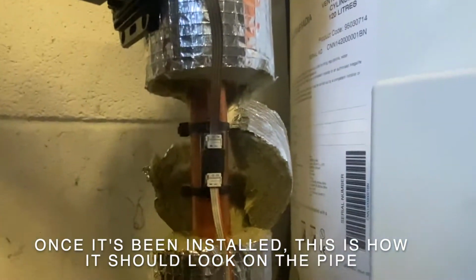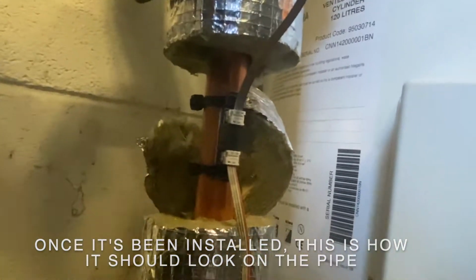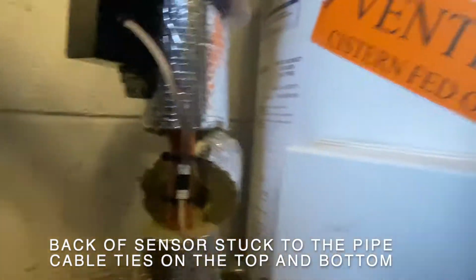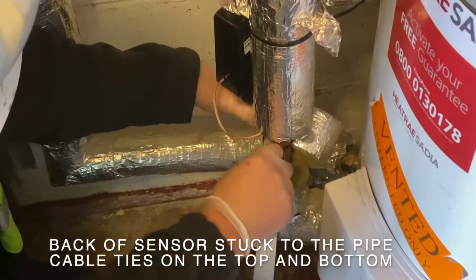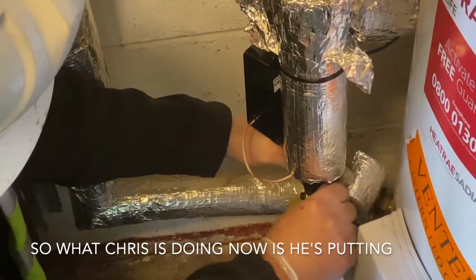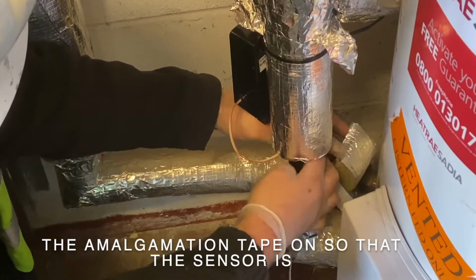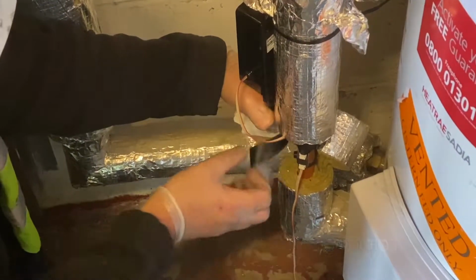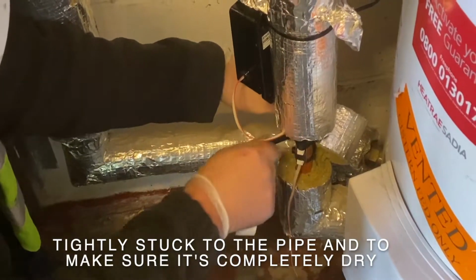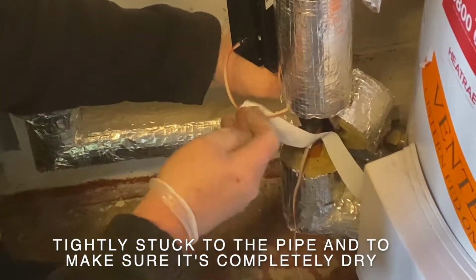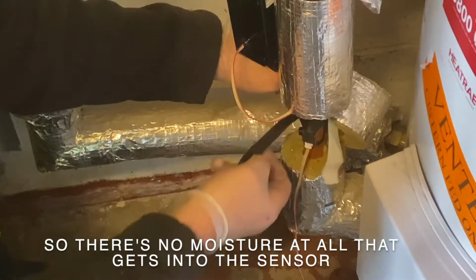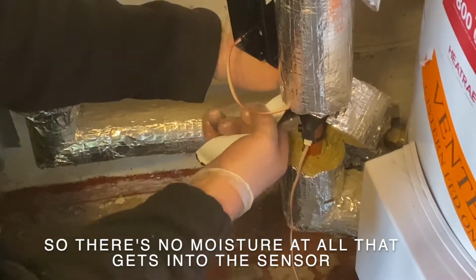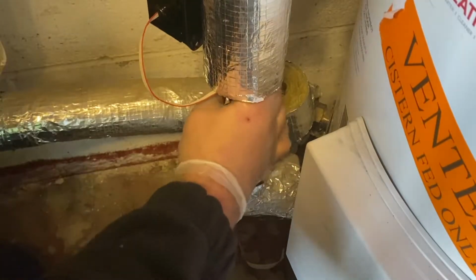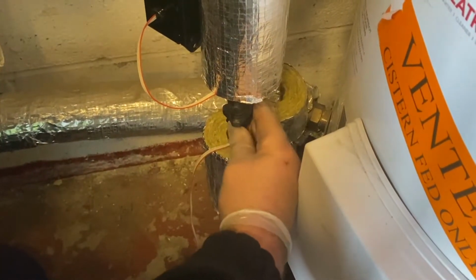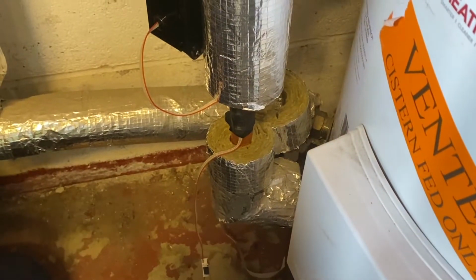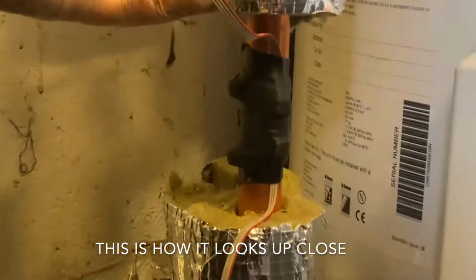Now once it's been installed, this is how it should look on the pipe. So back of the sensor stuck to the pipe and cable ties on the top and the bottom. So what Chris is doing now is he's putting the amalgamation tape on so that the sensor is tightly stuck to the pipe, and also to make sure that it's completely dry inside so there's no moisture at all that gets into the sensor. Of course, we don't want that. And this is just how it looks up close.